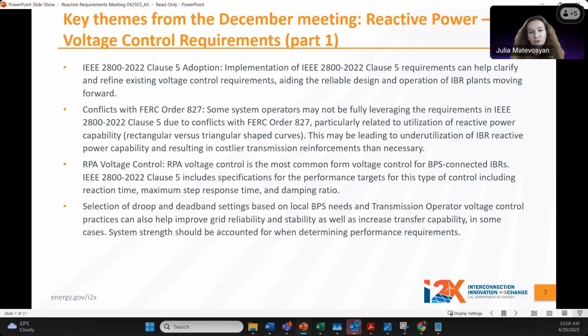Reference point of applicability for voltage control: the most common way of control is voltage control, not constant reactive power, but voltage control mode for BPS-connected IBRs. 2800-2022 includes specifications for performance targets for this type of control, including reaction time, maximum step response time, and damping ratio. Selection of gain and deadband settings based on local BPS needs and transmission operator voltage control practices can also help improve grid reliability and stability and increase transfer capability in some cases. This was something BPA extensively brought up in the meeting, discussing their best practices and experience with using voltage gain for voltage control.